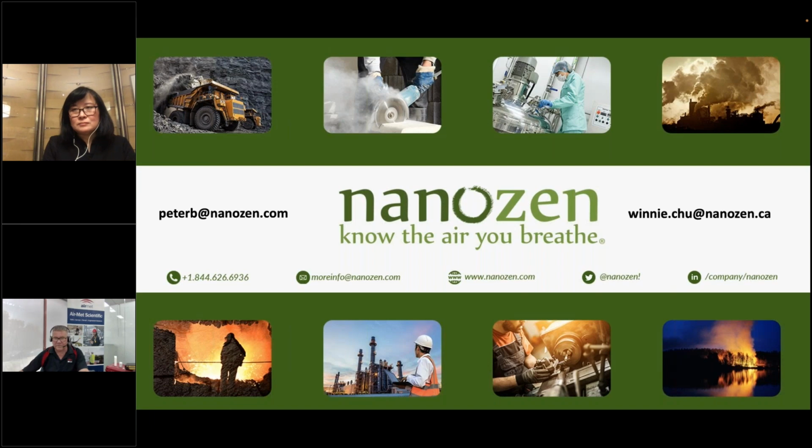I've got a question from Ben: how does the Nanozen pump cope with very high concentrations? We have done some work with other sites. If the concentration is higher than what we can handle, there are ways of adding an impactor outside the monitor to impact out anything larger than 10 micrometers, which we don't care about. We have done that, but you need to add another impactor.